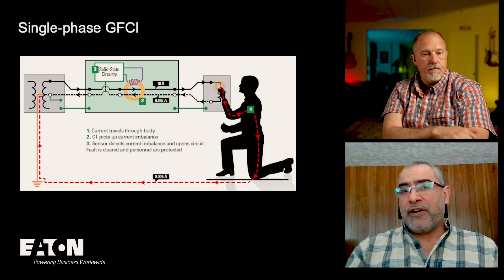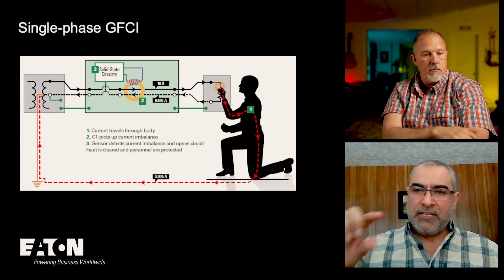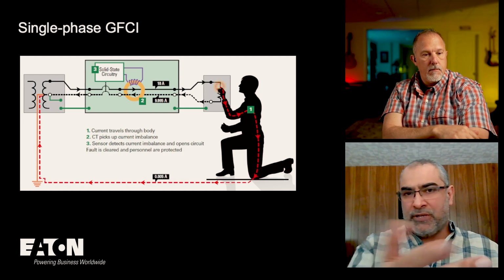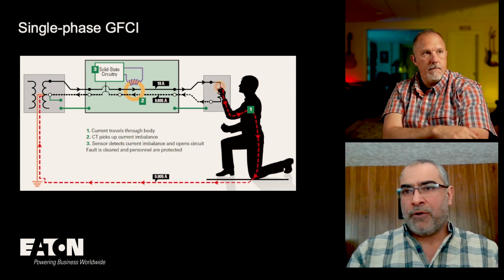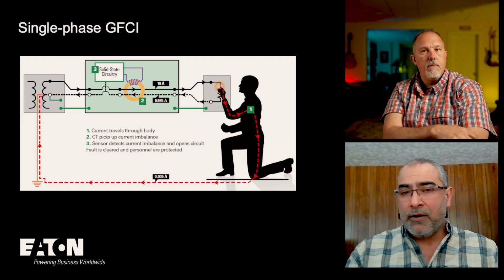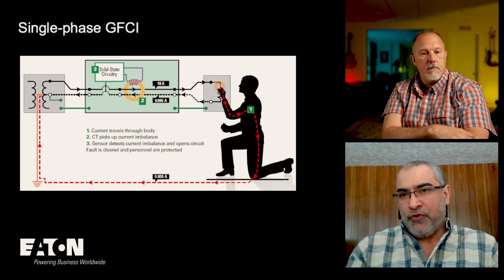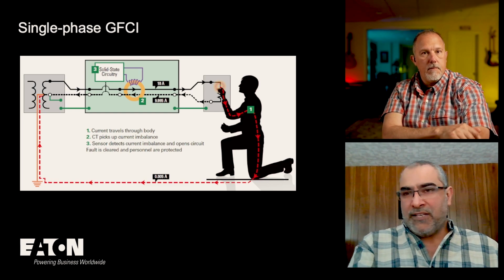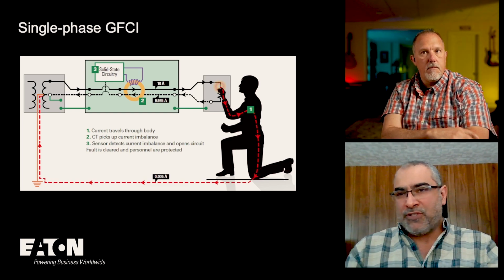There is 500 ohms inserted in the circuit, and this represents the person in the image Tom's showing on the screen. We know 500 ohms is very conservative - most likely the resistance will be higher, but that's safer, because if you insert a higher resistance, there's less amount of current, so it's safer.